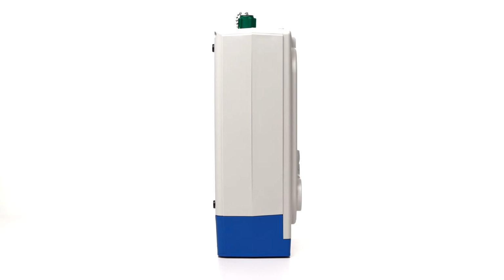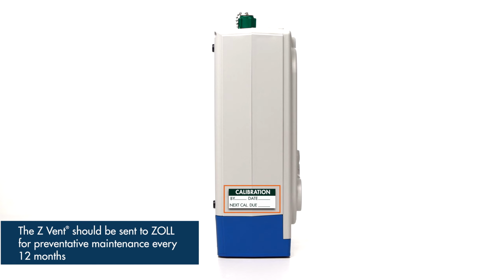Now we will look at the right side of the device. This is where the service and calibration information is located. This label provides the date of the device's last calibration and when the next service is due. The Z Vent's calibration is checked as part of the annual service procedure. The Z Vent should be sent to ZOLL for preventative maintenance every 12 months, or if the device is ever not functioning properly.